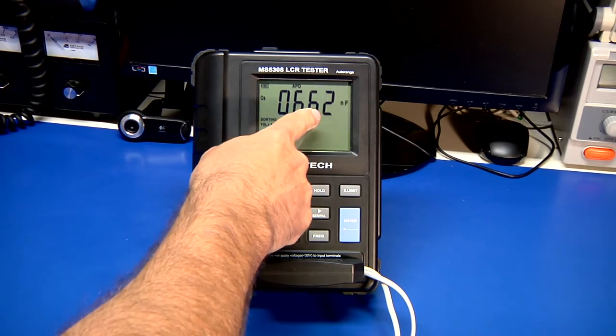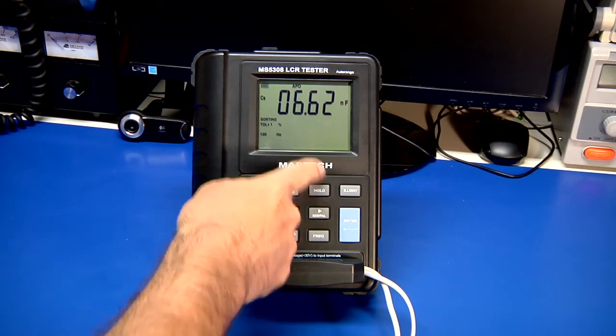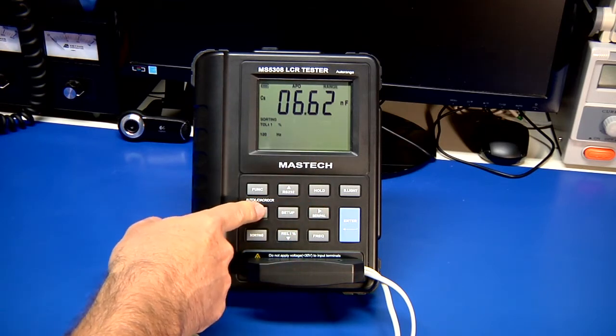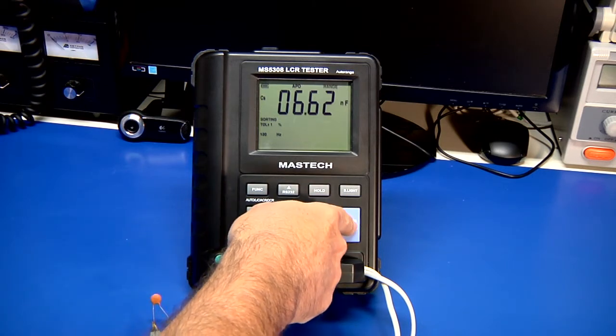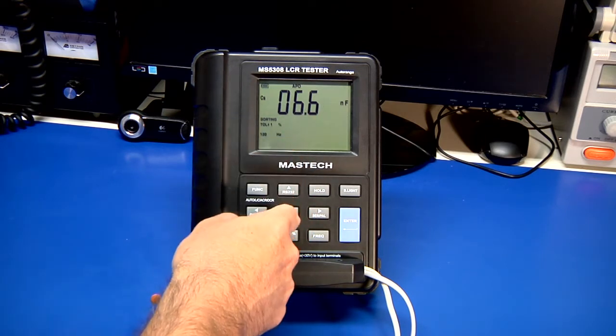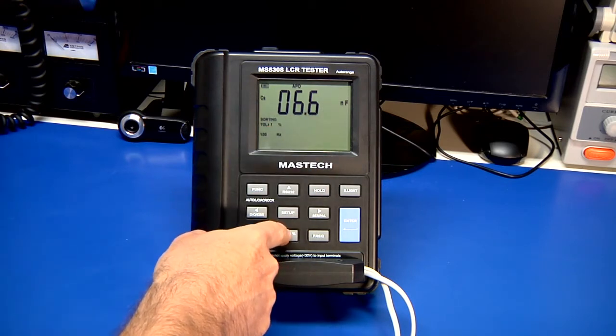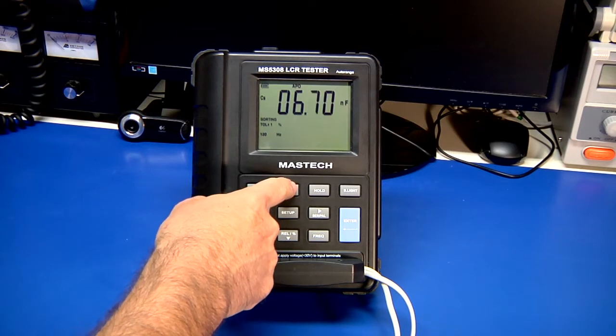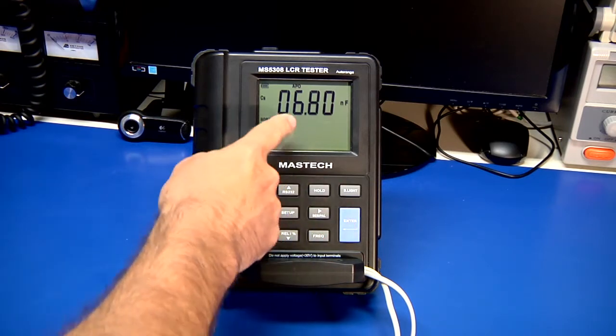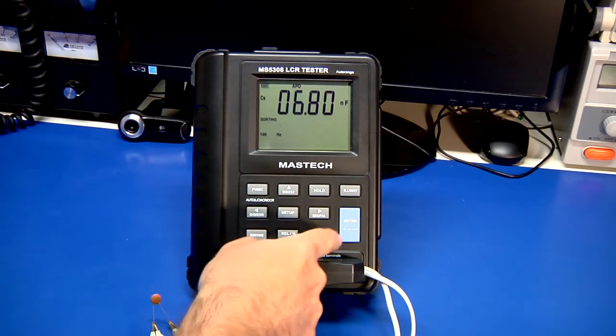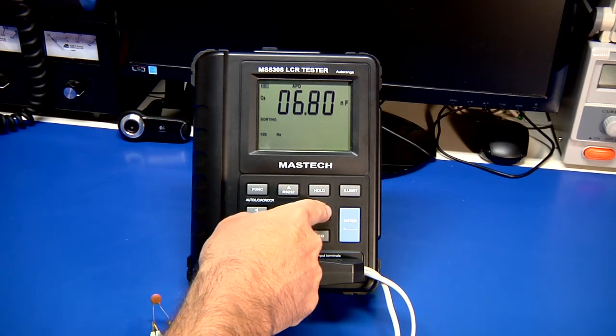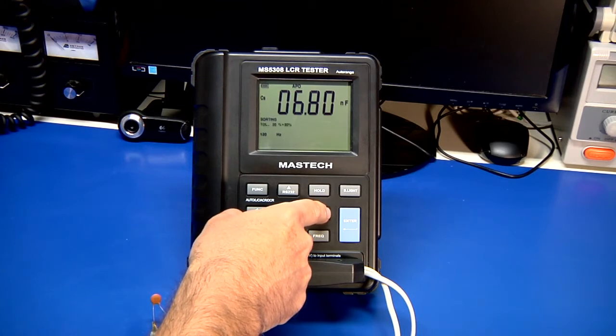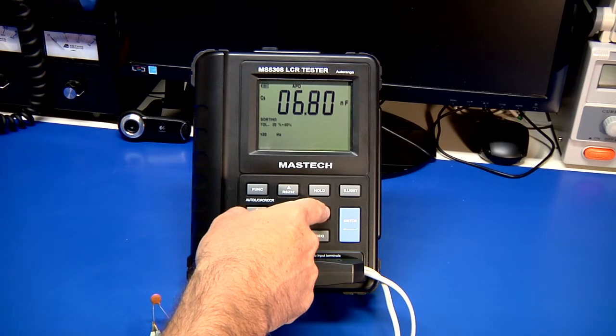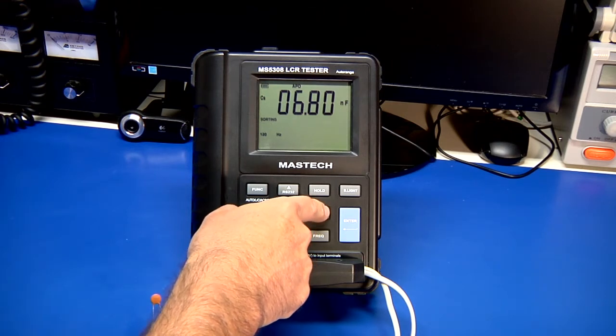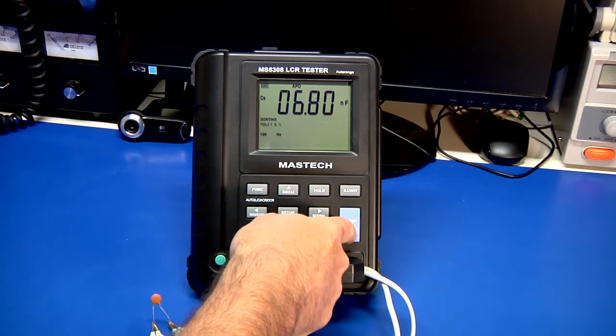So if we press setup, we can go through here and we can choose the range by using these two arrow keys. So if you notice we're at 6.6, and you see each time I press it, it moves back and forth across there. So I'm going to just leave it where it is, press the enter key, I'm okay with that, and then now it allows us to change it. Since this is supposed to be a 6.8, I will just use the down arrow keys to take the least significant digit down to 0, then move over one, and I want to take this one up to 0.8, and then press my enter key. And now this is my new value. It's asking us what tolerance, and you can cycle through the different tolerances. We have 1% there, 2%, 5%, 10%, 20%, minus 20 plus 80%, which sounds strange, but that's for electrolytics and filter capacitors. And then we can go down to 1/4%, 0.5%, so quite a few choices, 1%. I'm going to go ahead and set it up for 10%. So there's my 10%, press enter, and we're ready.